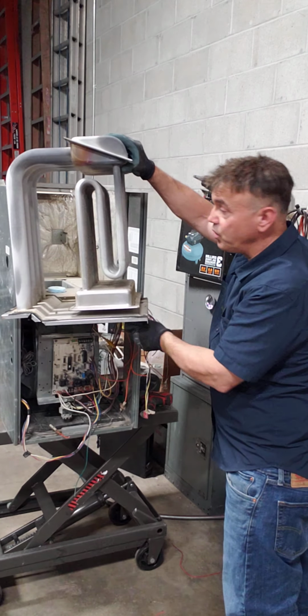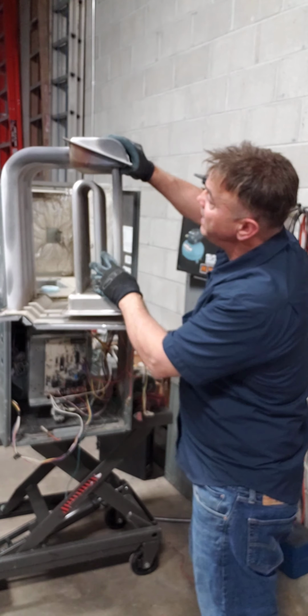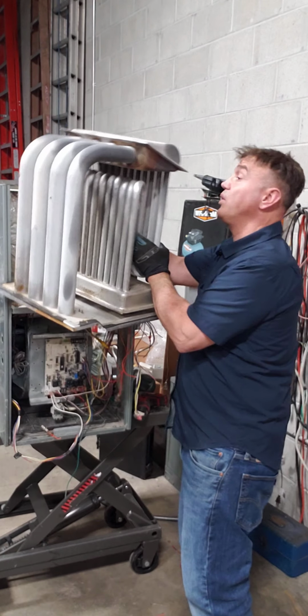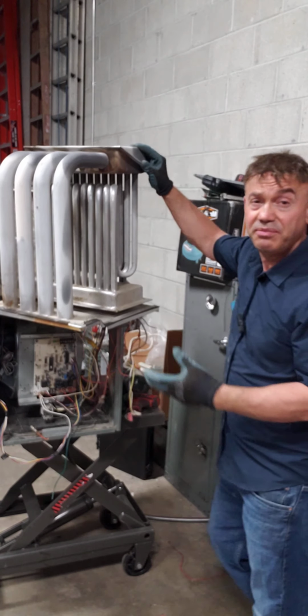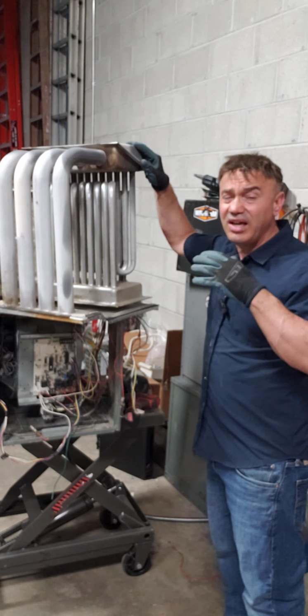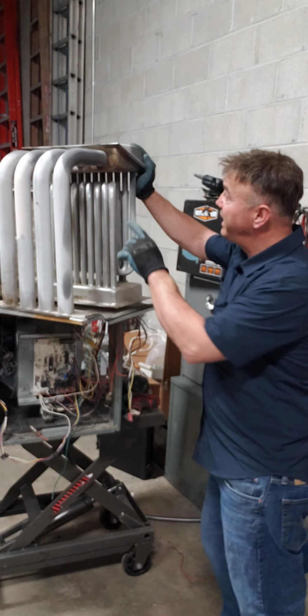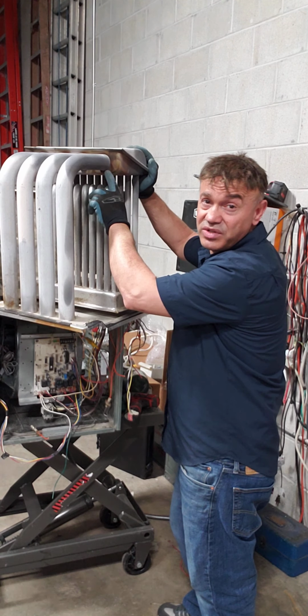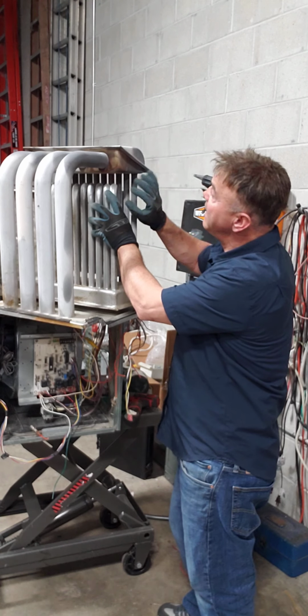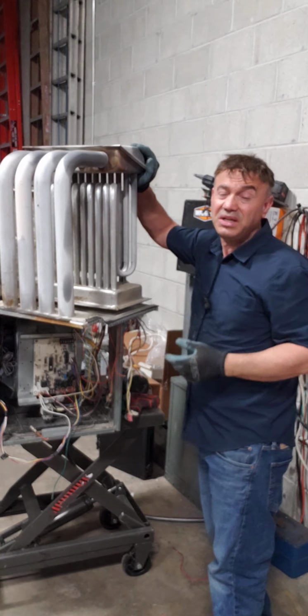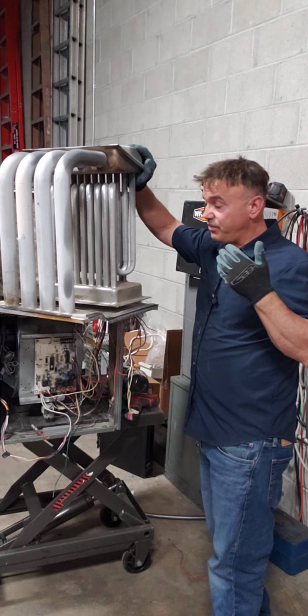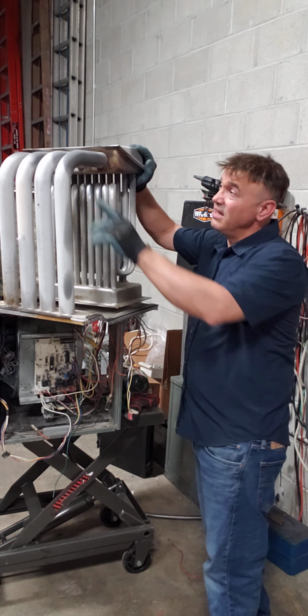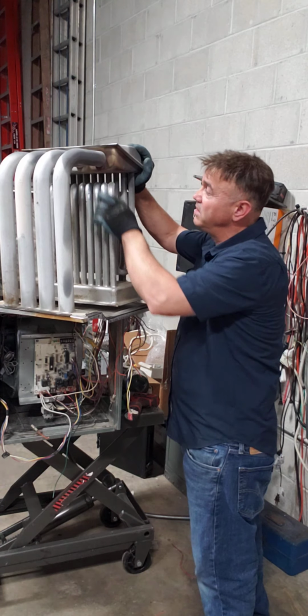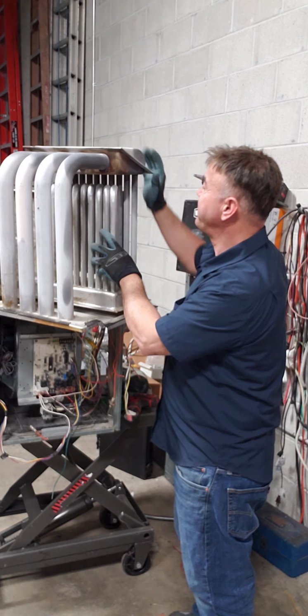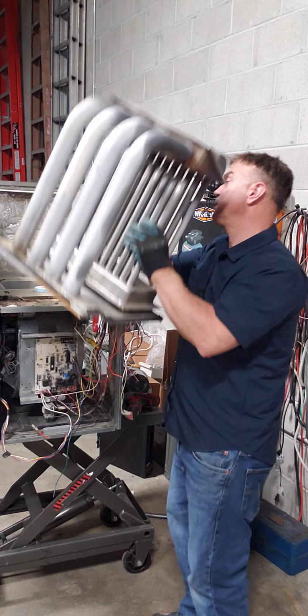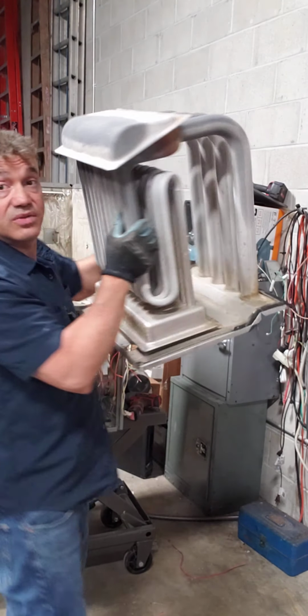And here you have the inducer motor. Remember? A lot of times, how I know if the gas valve was really sending a lot of extra gas into the furnace is when you see damage on the heat exchanger. You can see it, right? See, at some point, maybe if this was running and it was freezing outside, and the furnace ran an extra long time, this thing can be almost orange. So it's been abused. But again, this heat exchanger really is nice. I like the way they do it. See that?